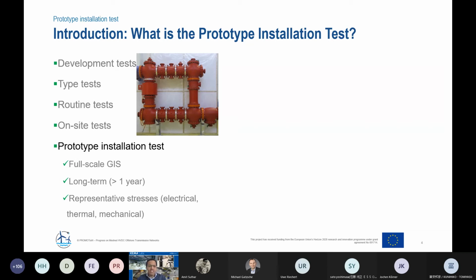So it's a full-scale GIS, and the test itself is special in a way that it is not a short time test. This is a long duration test which lasted more than 1 year, basically in a laboratory, applying different types of tests. And in this test, all the representative stresses, as it would be in service, are applied: electrical, thermal, and also mechanical.